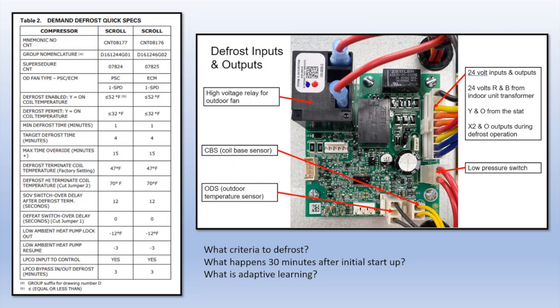The reason that needs to happen is so that it can populate an error code on the fault status, the fault light, which is red, and also so it can count the low pressure switch failures, so that once it reaches a certain number, it's going to go into a hard lockout until there's a reset in power. We also have the coil bottom sensor or coil base sensor, which is the yellow wires. And then we have the black wires, which is the outdoor temperature sensor. And then we have our forced defrost pins here, and a couple of jumpers we'll go over.